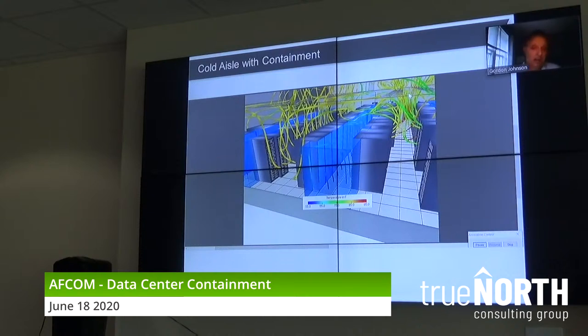Now look at the hot air coming from the exhaust. It tried to get around the end of the aisles. It tried to go over the top of the racks because hot air goes where it wants to go. But in this case, it gets rejected. So eventually it says, I've got nowhere to go, but eventually I'll make my way up through those ceiling grills and back to the returns on my CRACs. This is a case where we spoke about earlier.